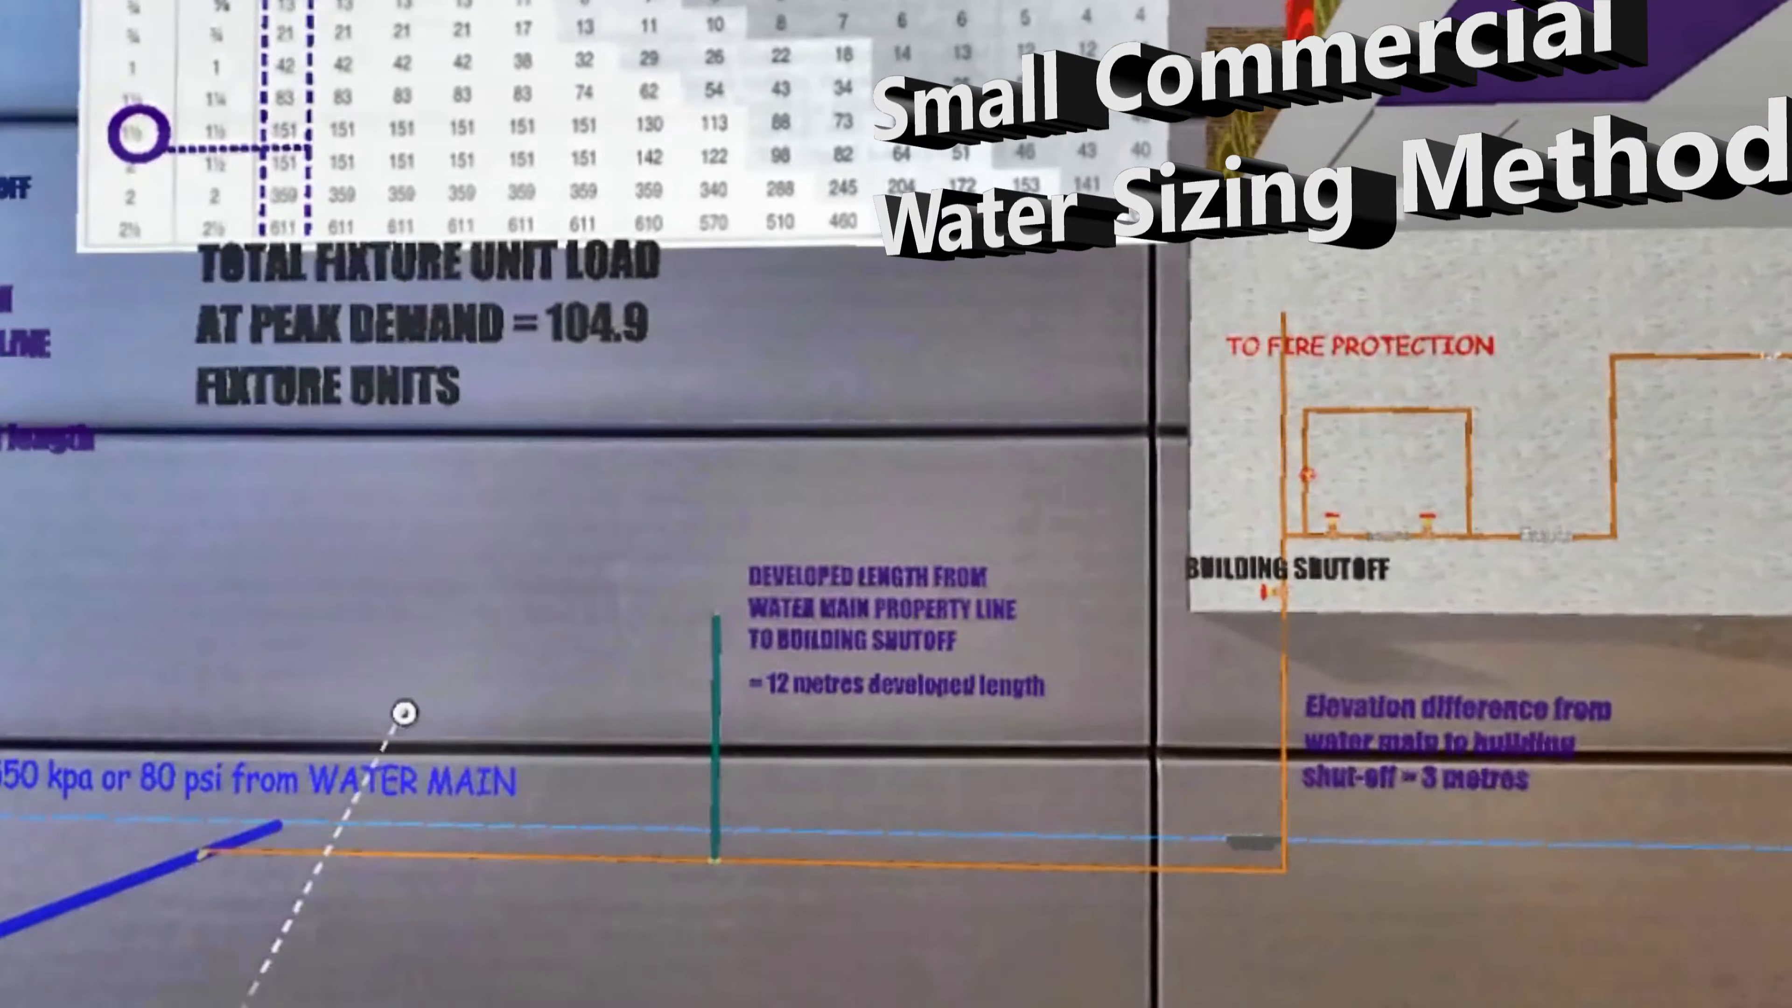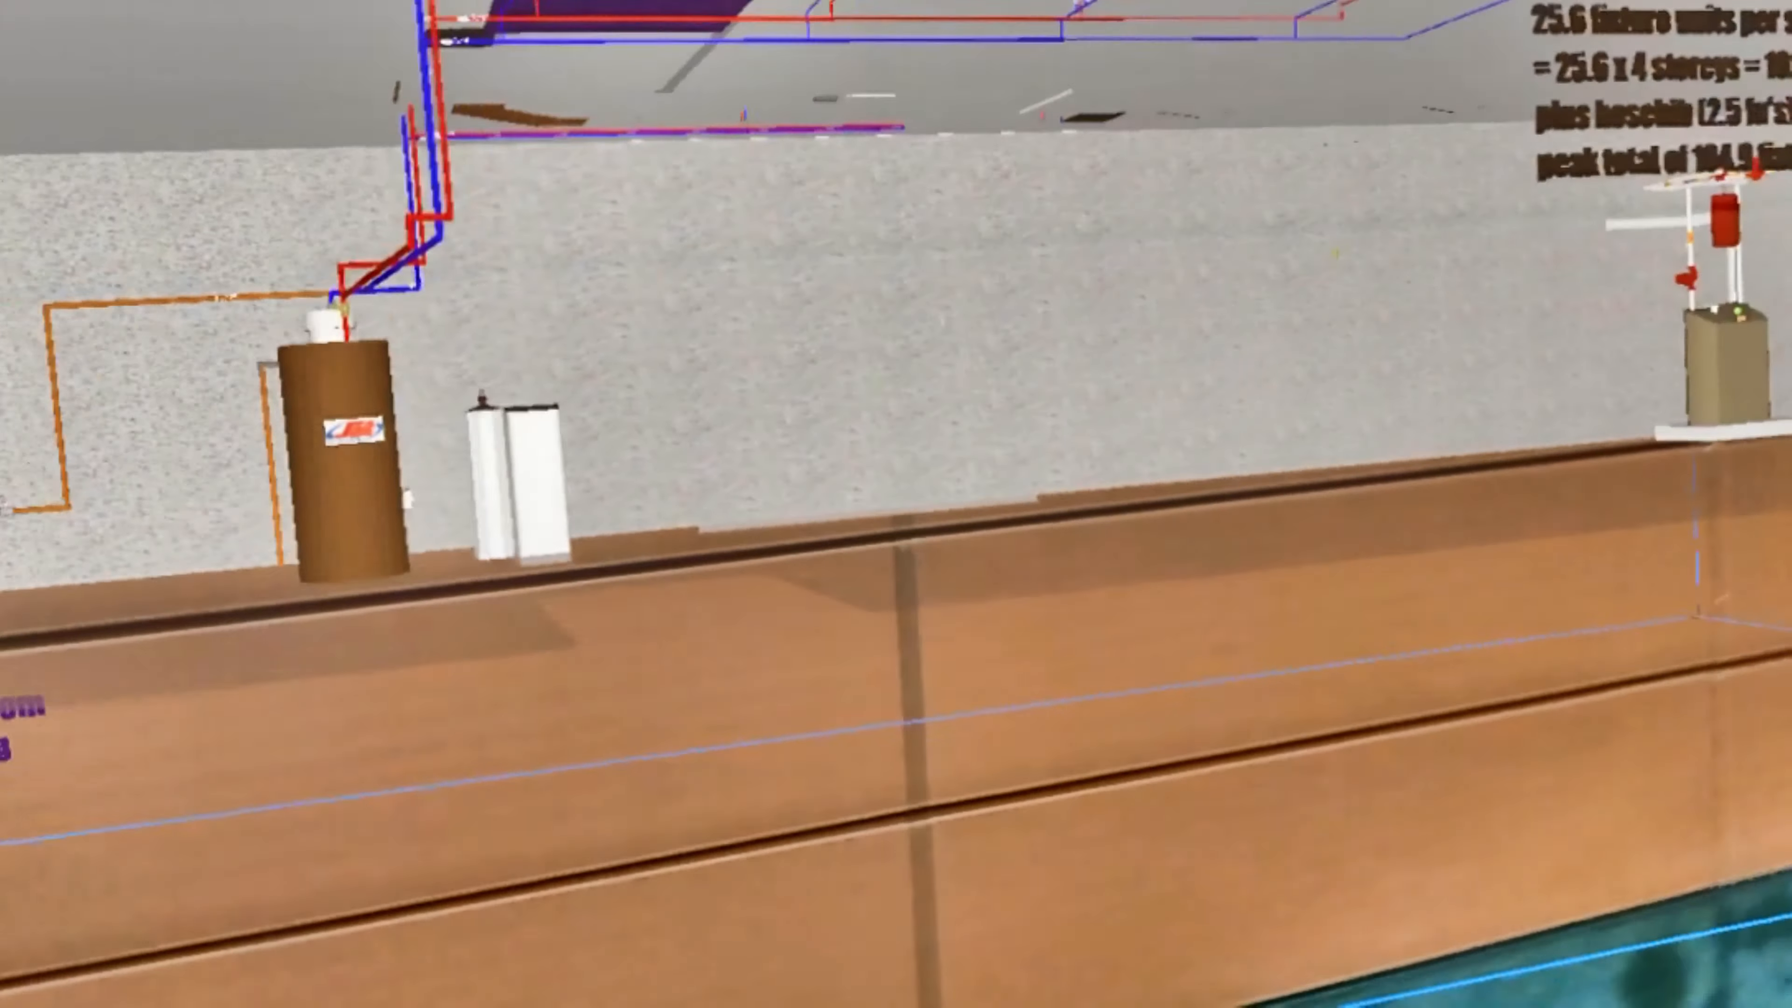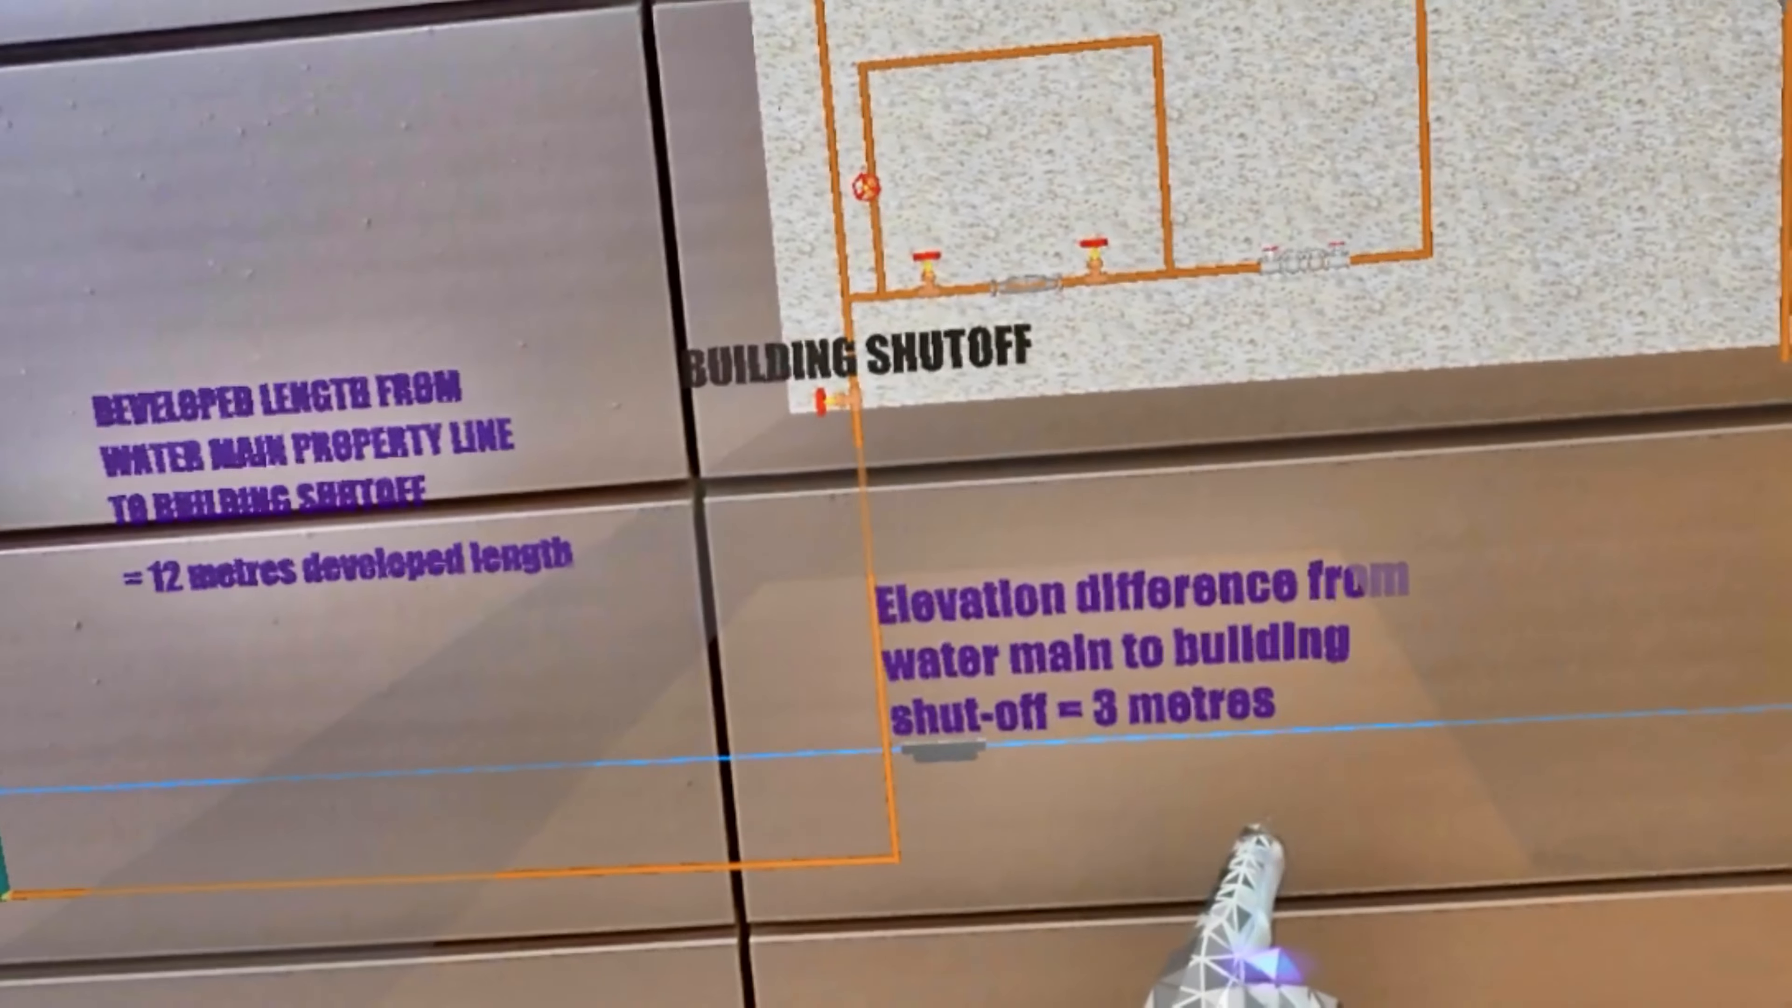The water service is right here from the curb cock right here to the building shutoff, and that is 12 meters long. So you use the 12 meters developed length, then you use the total fixture unit load of the building which I've already figured out is 104.9 fixture units. And then the last thing is you just need the elevation difference from the water service to the main shutoff, which is 3 meters.